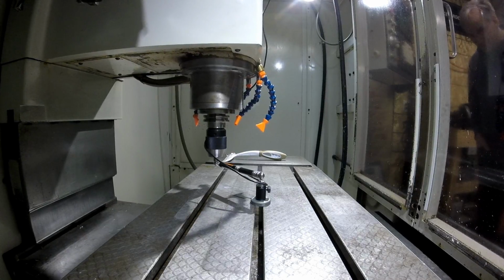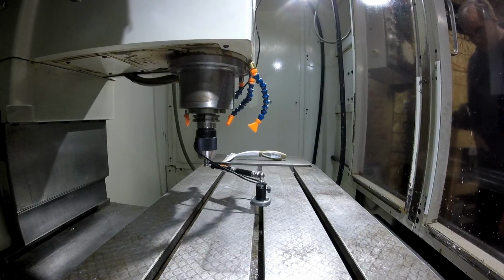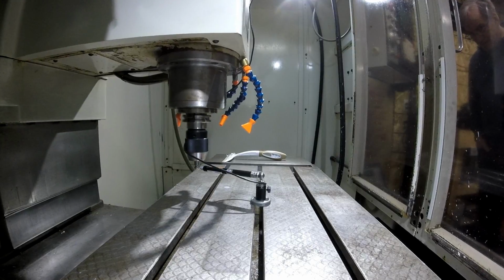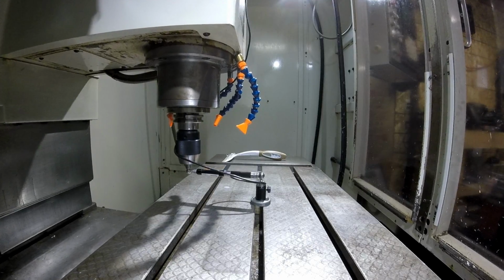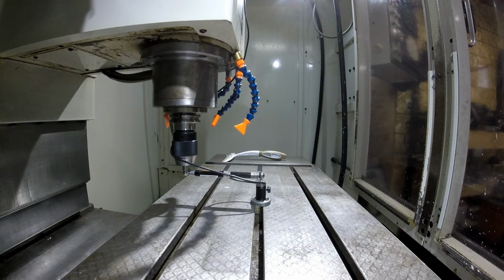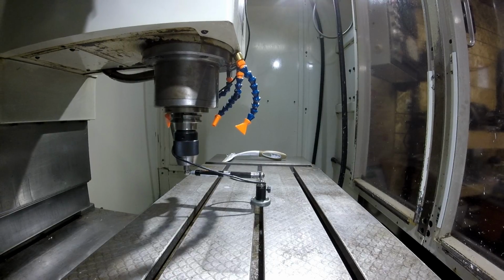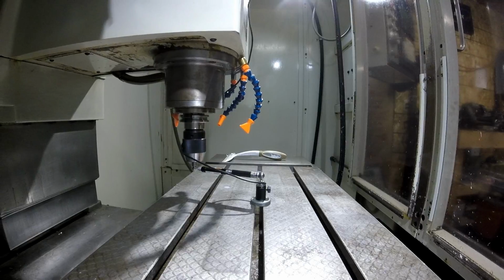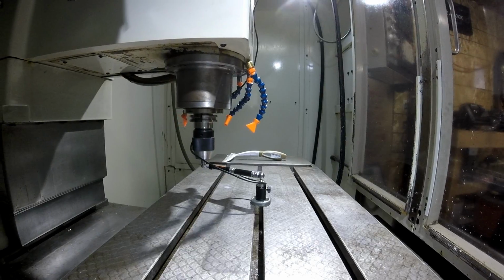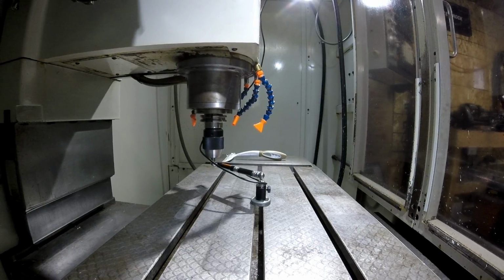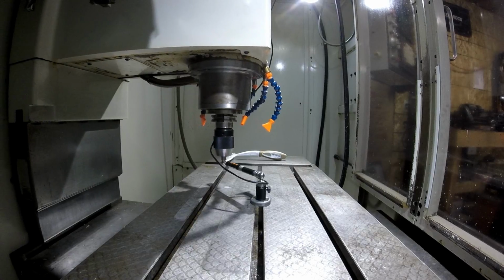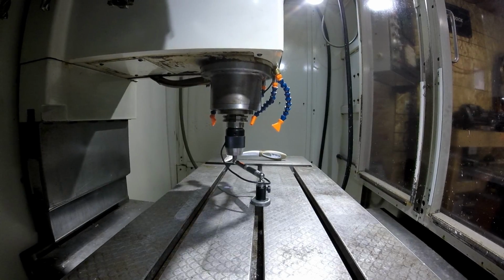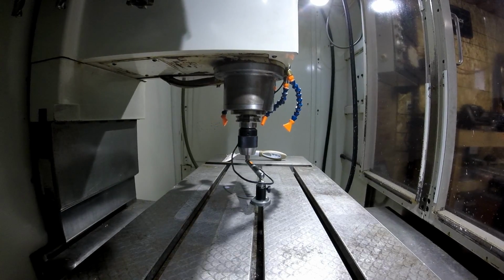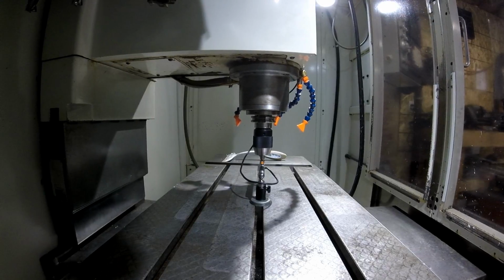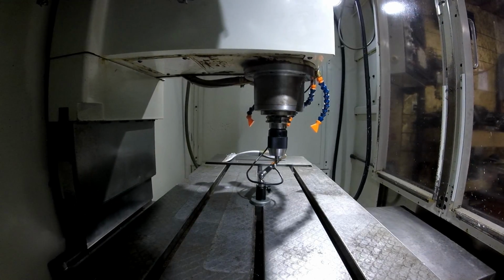Also, by knowing where it's starting and stopping and what time it's starting and stopping, that's how it synchronizes the positional measurements with the rotation of the circle. So it knows I'm at 12 o'clock, or I'm at 6 o'clock. So it uses it by time. There are no encoders or angular sensors in this thing. It is strictly just a linear displacement sensor with a lot of really smart, good software behind it.